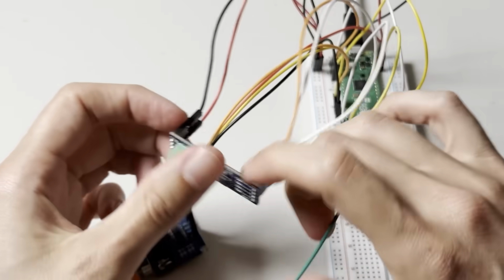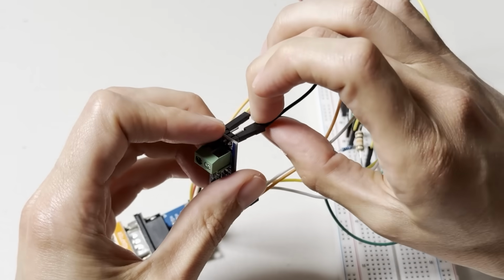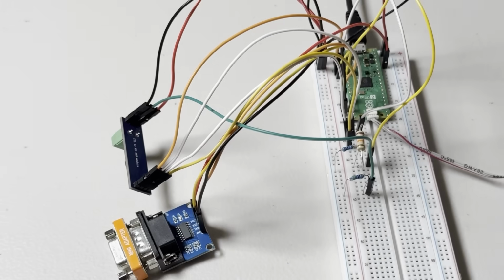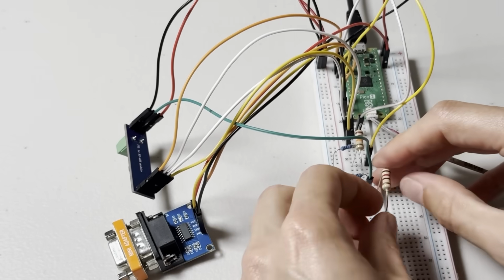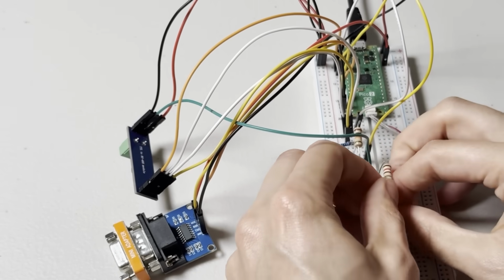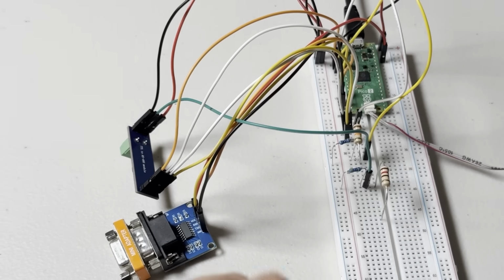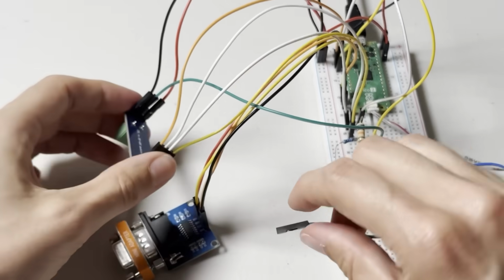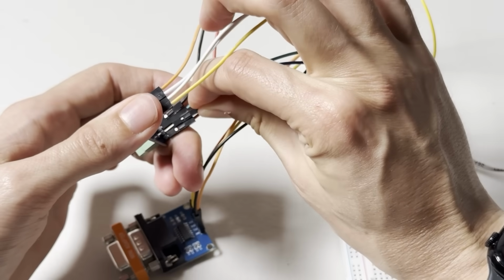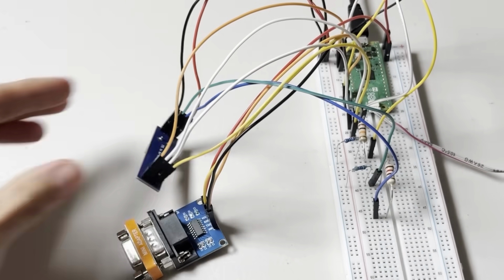RS-485 uses differential signalling, meaning there are two wires and the signal is encoded in the voltage between them. To avoid noise, we need to keep that voltage at a known level even when no one is transmitting, so we'll add pull-up and pull-down resistors. We'll also add a termination resistor between them to minimise reflections of the signal.